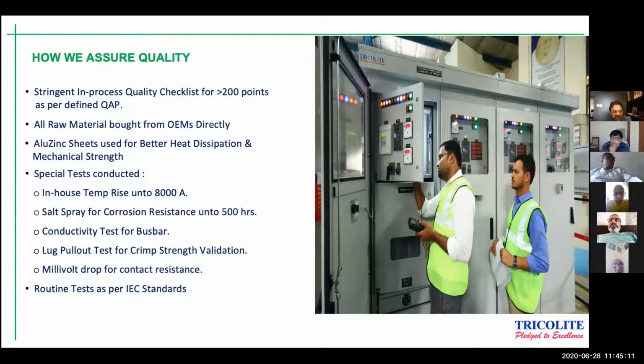We also regularly check the millivolt drop for contact resistance for all higher rating breakers, 3000 amperes and above, for all breaker joints and busbar connections. This is a wonderful test that helps us verify the quality of our assembly.